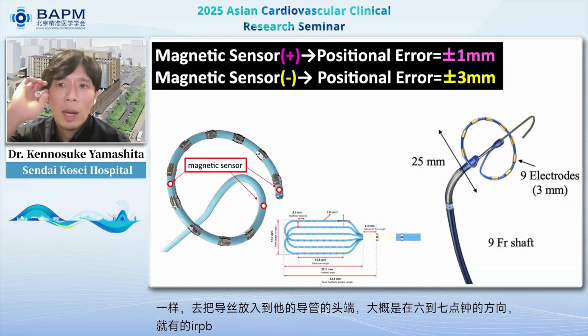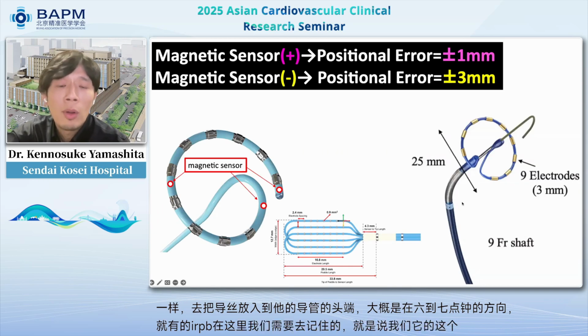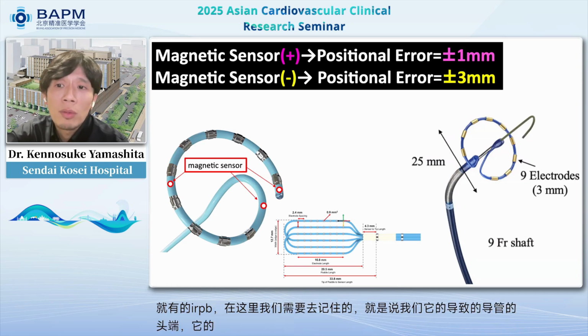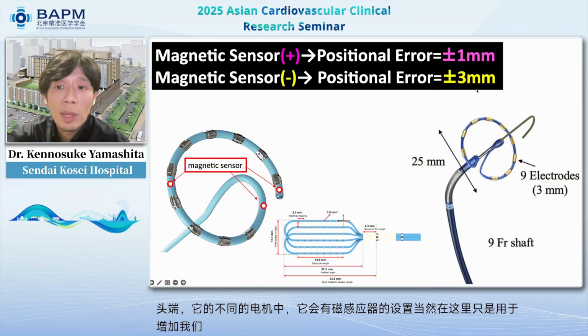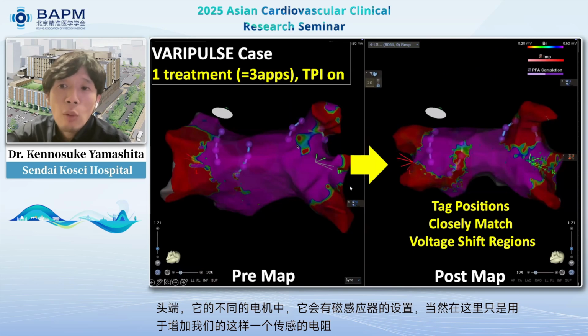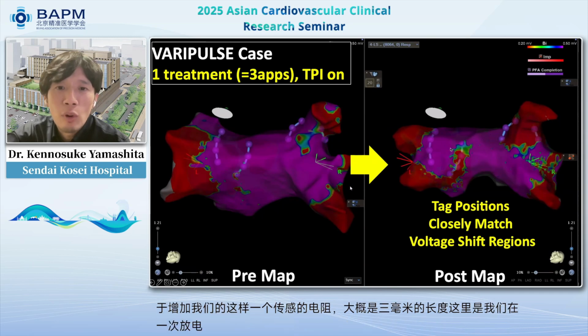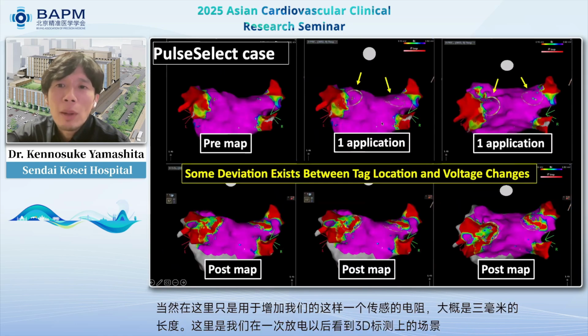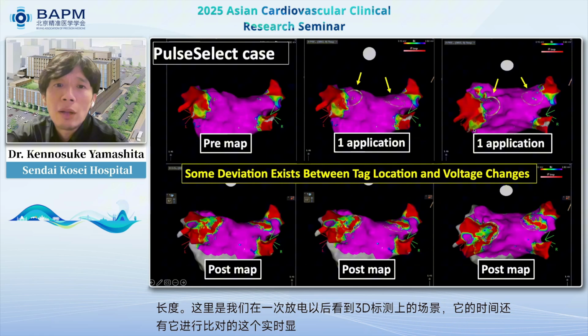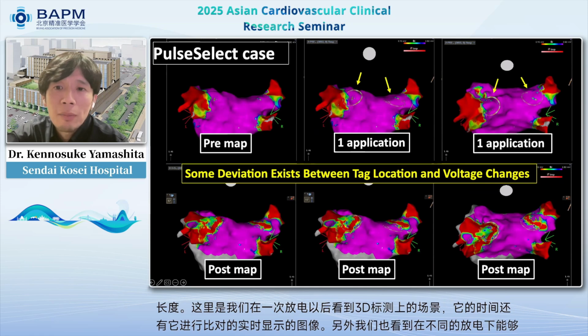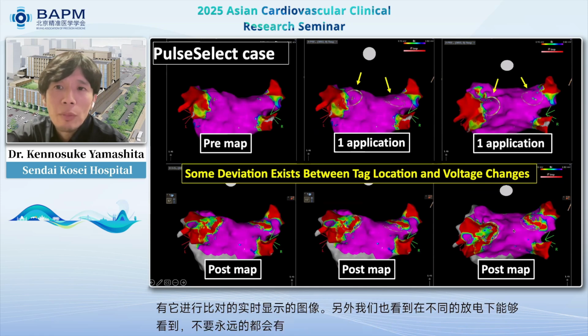One thing to note: the VARIPULSE catheter has a magnetic sensor, but the PulseSelect doesn't have a magnetic sensor. It uses impedance-based tracking only, so position error is plus or minus 3 mm. Here's the voltage map after one VARIPULSE application. The region tag and the area of low voltage align well. On the other hand, with the PulseSelect, the snapshot position and actual voltage drops don't always match like that. We need to recognize this limitation.